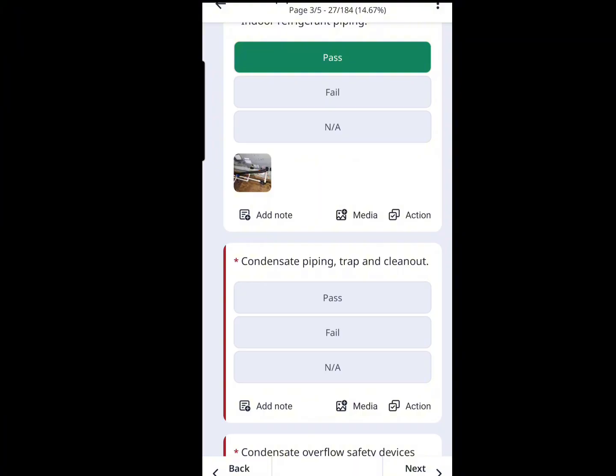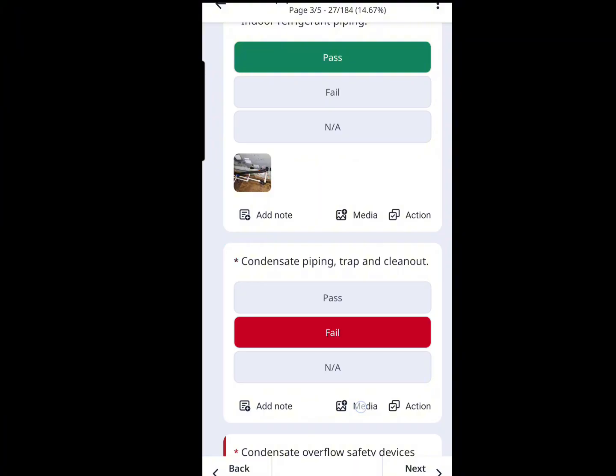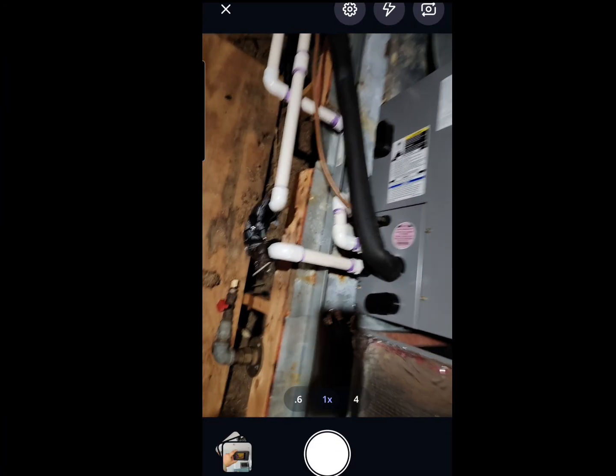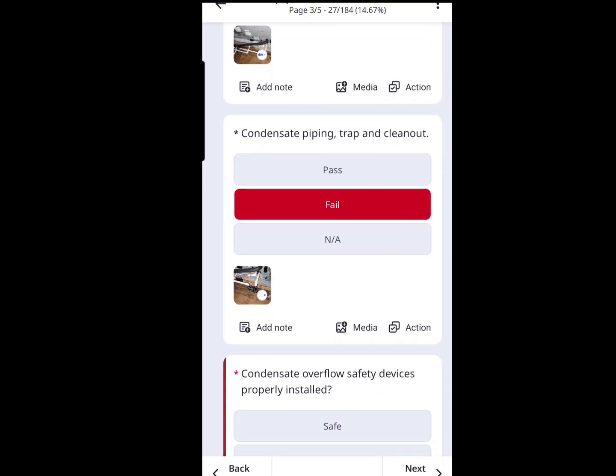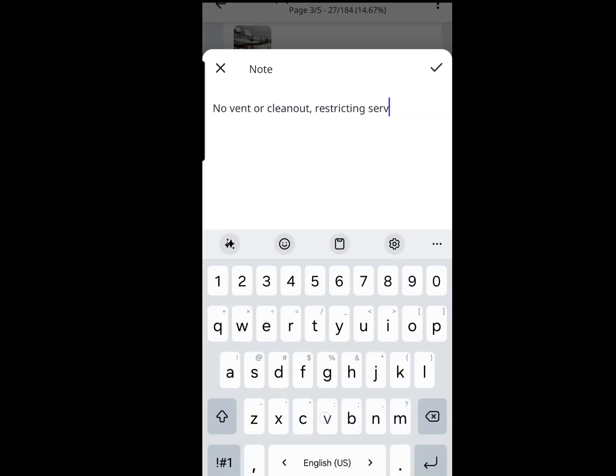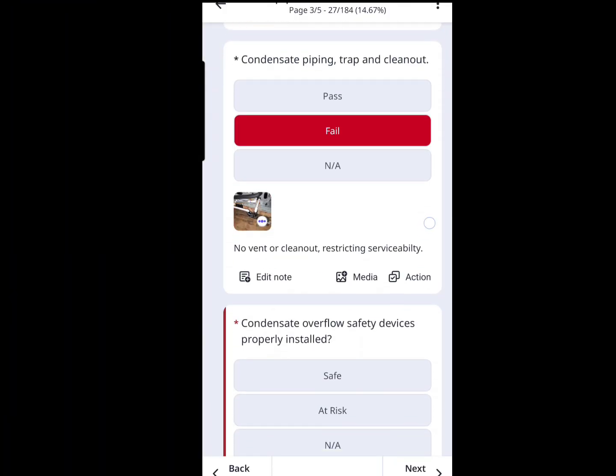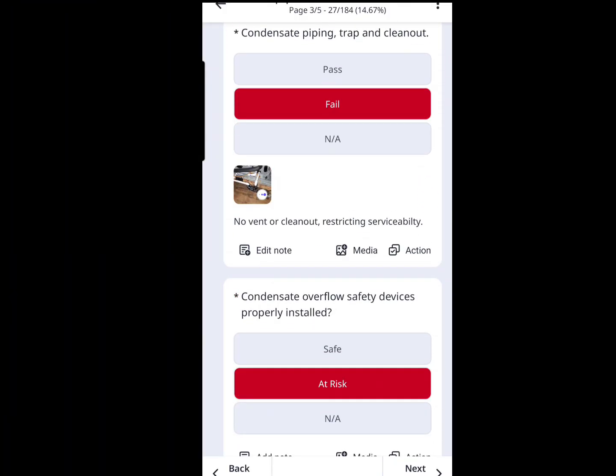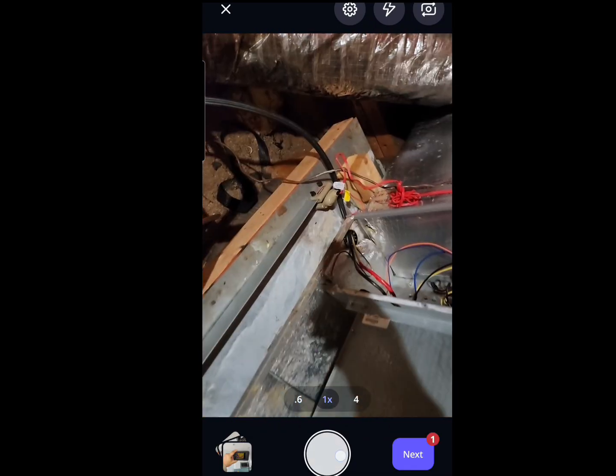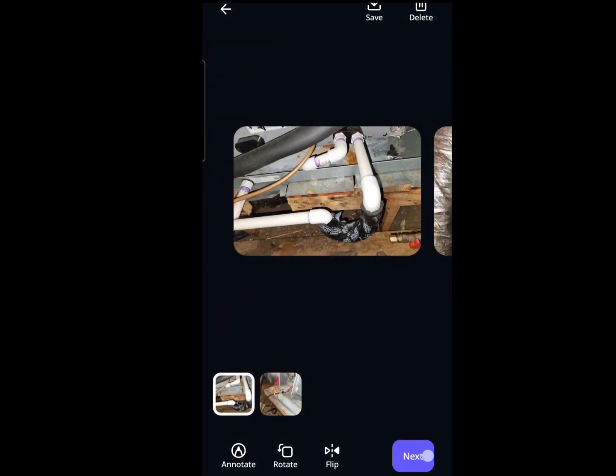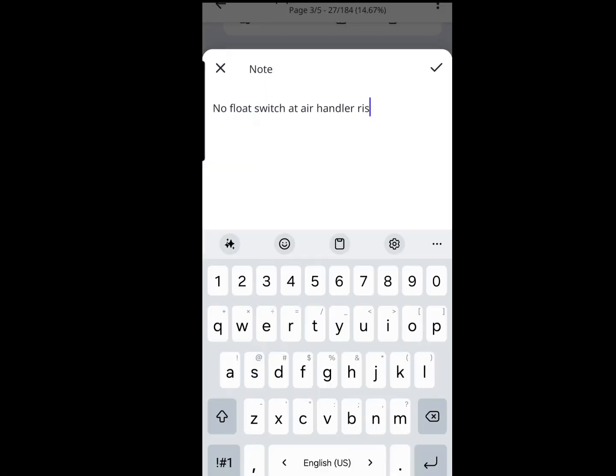Next we move on to condensate piping. I'm looking to make sure it's piped correctly, with good pitch, a clean-out, and a vent — and it looks like we're lacking some of those things. Then I look for condensate overflow safety: we need enough float switches to cut the unit off in case the pan overflows. Looks like they're missing a float switch at the air handler. There is one at the pan, but we can stop a water leak a lot sooner with one at the air handler too. We're going to make a note of that and offer it as a recommendation at the end of the call.